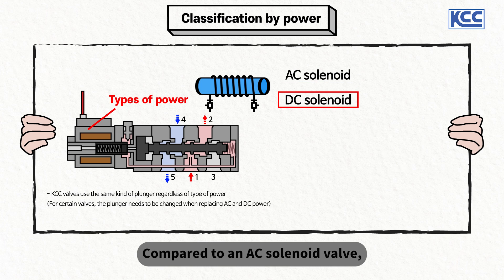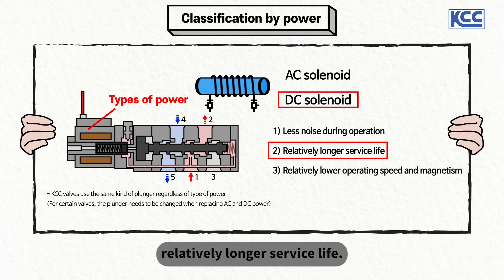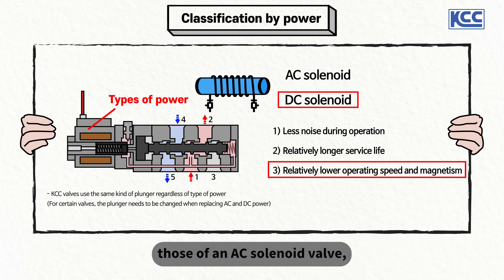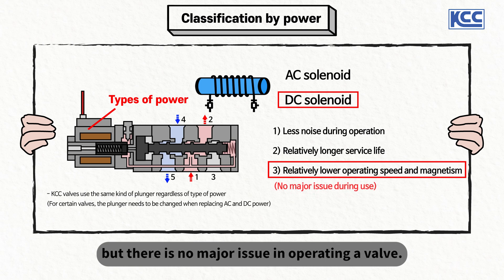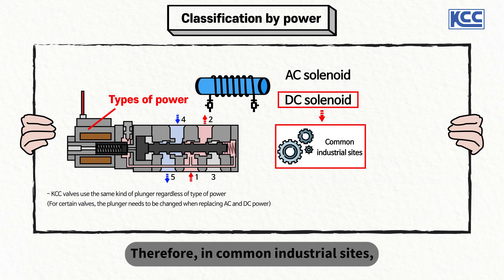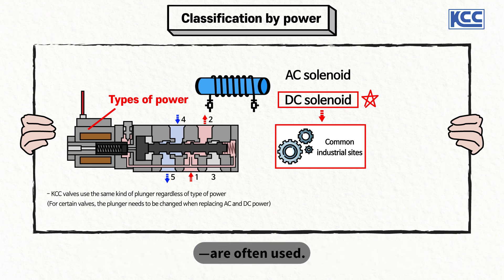Compared to an AC solenoid valve, a DC solenoid valve is quieter with a relatively longer service life. Its operating speed and magnetism may be lower than those of an AC solenoid valve, but there is no major issue in operating a valve. Therefore, in common industrial sites, DC solenoid valves, which are more typically stable, are often used.